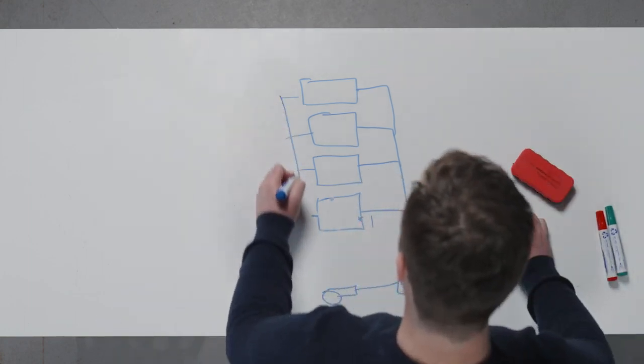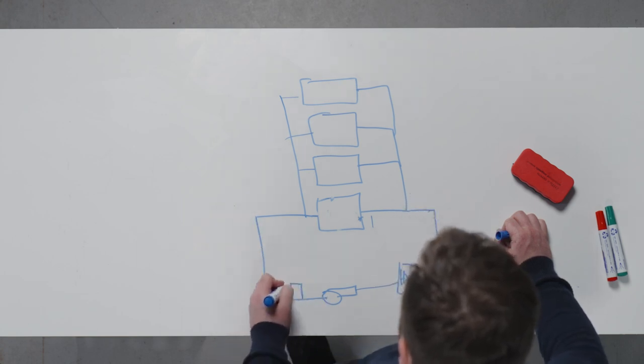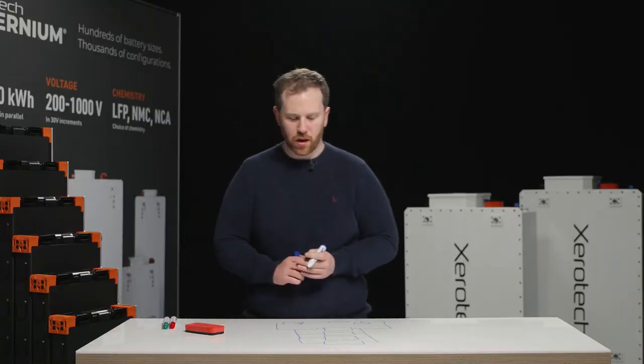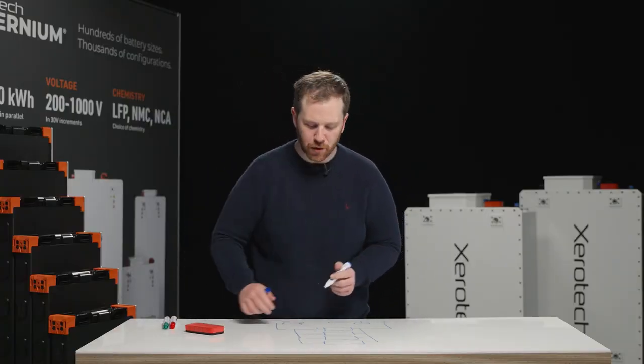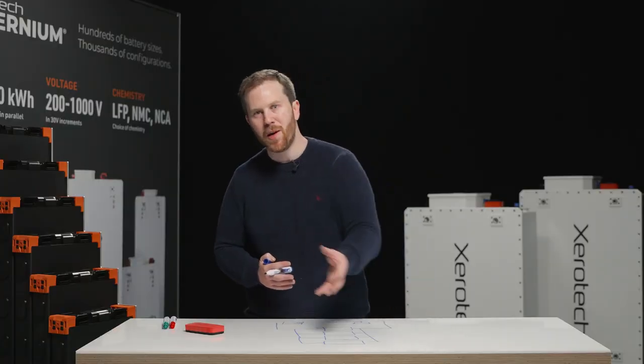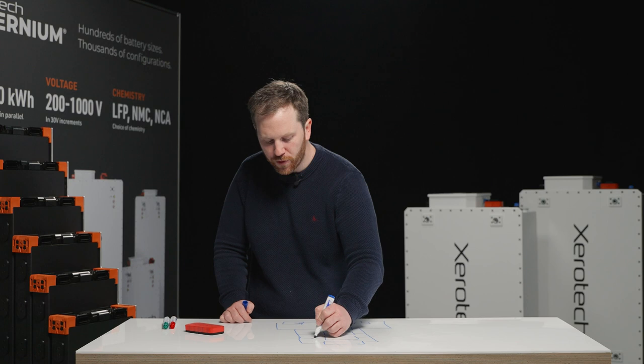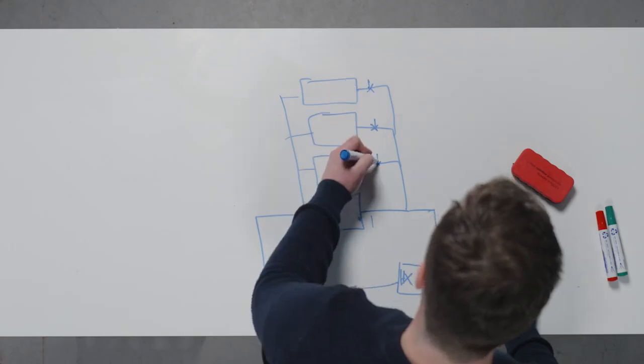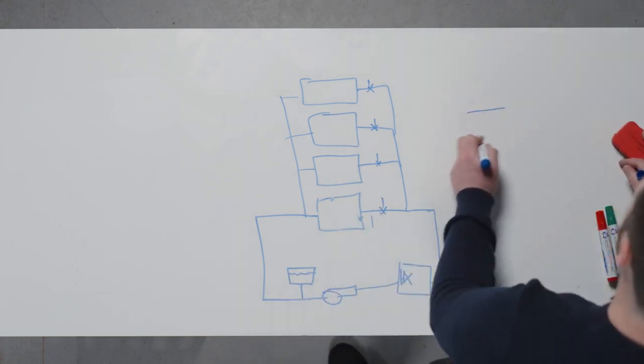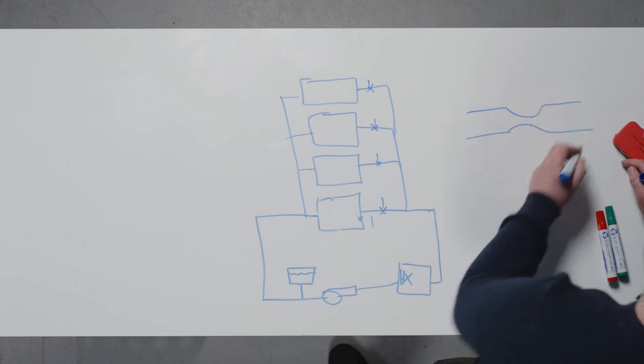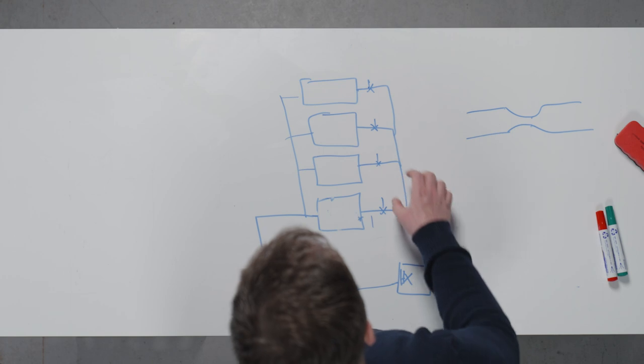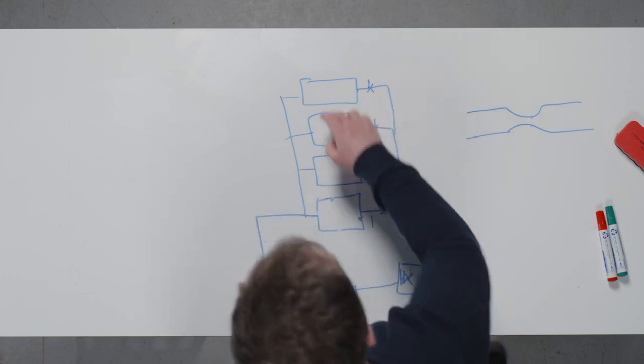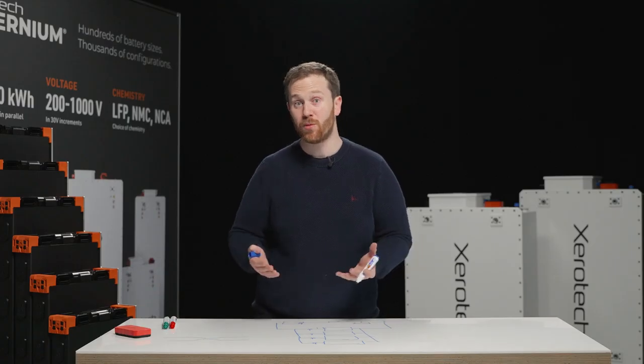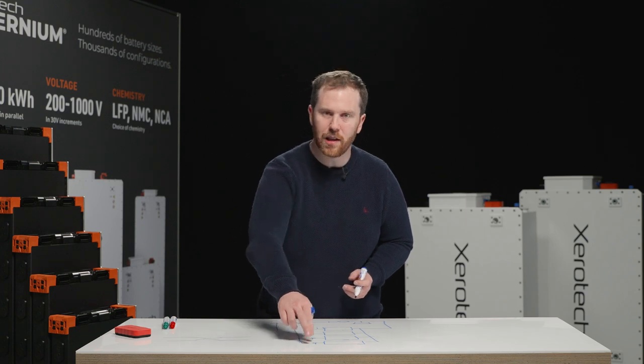So when we put these multiple packs in parallel, and it flows around to our circuit, and we put our header tank back in, one of the main watch out areas to look at here is you do want to have the packs roughly balanced. You want to make sure that all of your flow rate is not going through just one pack. In general, Xerotech battery systems have such a low pressure drop that they develop such a high flow rate that it doesn't really matter. You get very diminishing returns for excessive flow rate. But in systems where you've got any sort of throttling valves to balance the flow, what these valves do is basically intentionally choke down the flow to increase the pressure drop, because the length of the pipes here will have different pressure drops for each of these paths. And you might have heard the term that water takes the path of least resistance, and that's very true. So what you're trying to do is make sure the resistance in all these cases is even.